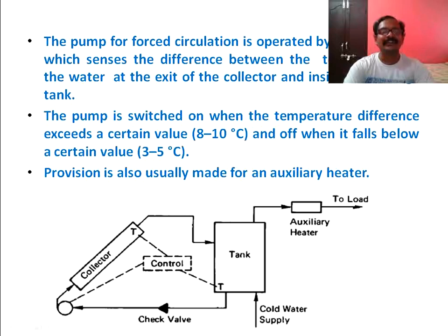and after sensing these two temperatures, it subtracts them. If it finds that the temperature difference between them is more than 10 degrees centigrade, it means the water inside the tank is losing its heat. That is, the hot water is becoming cold inside the tank after some time. So again that water will be pumped into the collector by switching the pump on. The water is pumped into the collector, the collector heats the water, and the water is again sent into the tank.